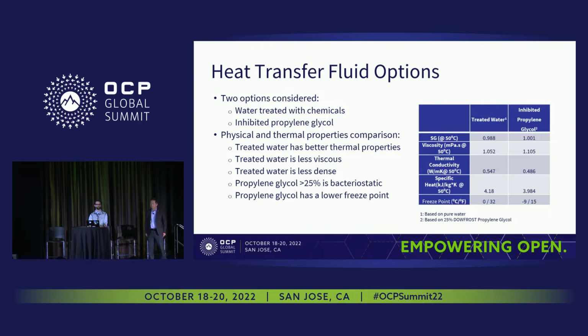There were two main fluids that were investigated as part of this workstream: water treated with chemicals and inhibited propylene glycol. Some of the most important considerations when looking at these two fluids are the physical and thermal properties. Treated water has better thermal properties, is less viscous and less dense. However, propylene glycol in concentrations over about 25% is bacteriostatic. Propylene glycol also has a lower freeze point.